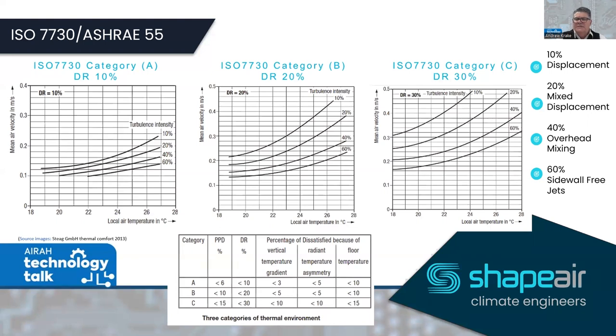10% turbulence intensity corresponds to a displacement system; 20% to a mixed floor swirl with induction and displacement; 40% to the majority of systems installed in Australia — mixed overhead systems with swirl, four-way, pattern, or perforated diffusers; and 60% turbulence intensity for something like sidewall registers. I'm going to concentrate on the 40% turbulence intensity for an overhead system.